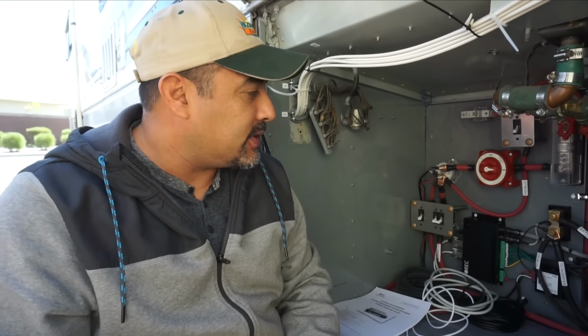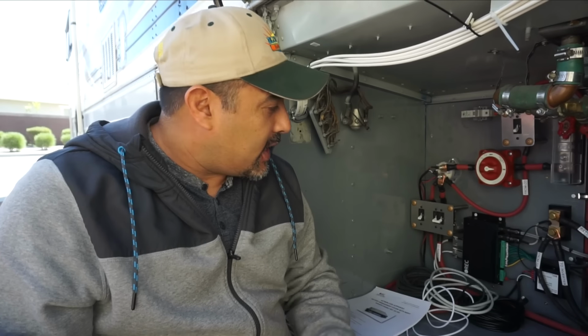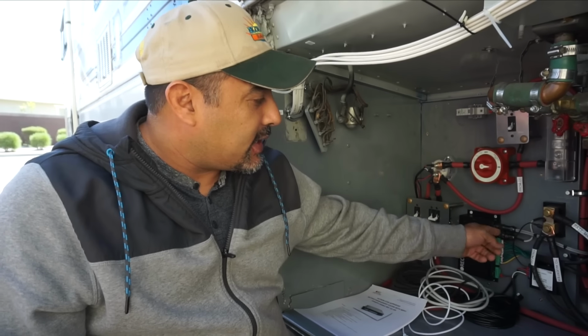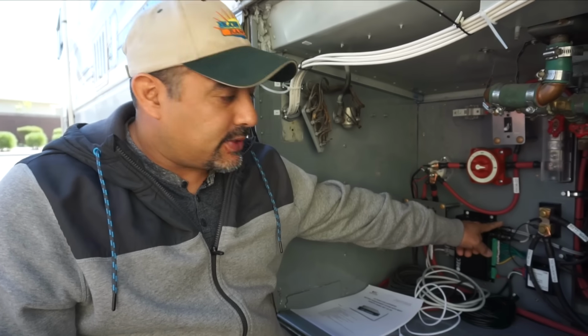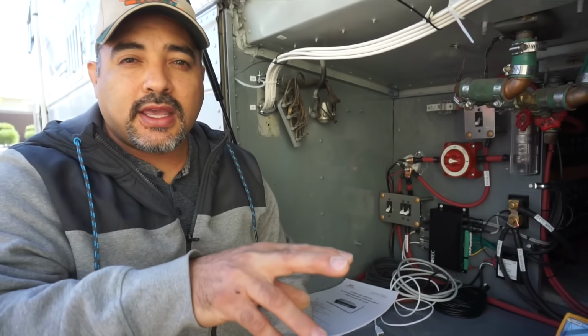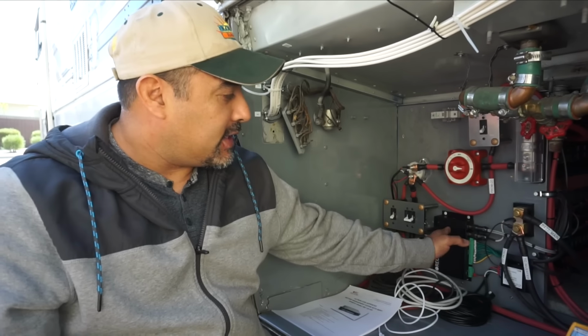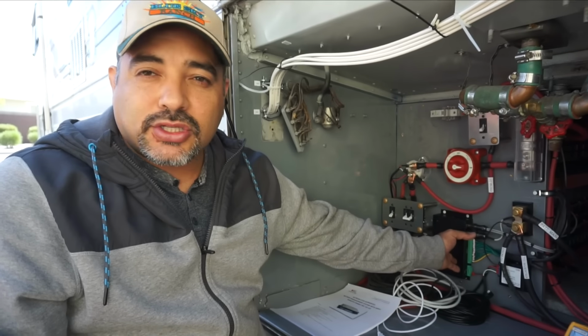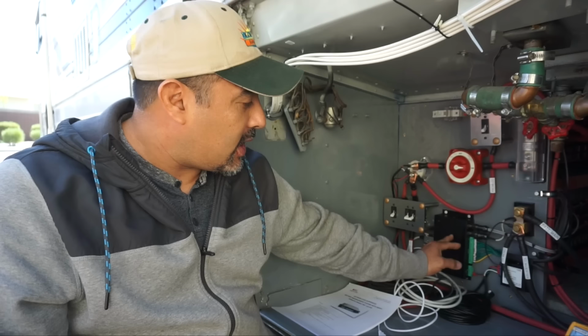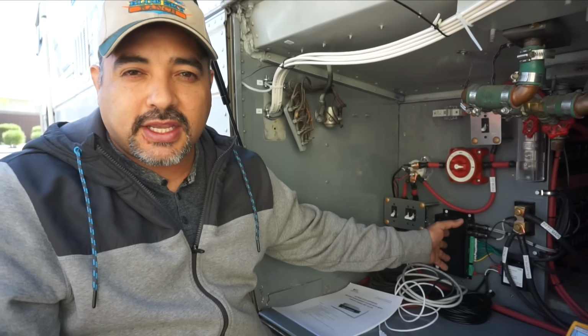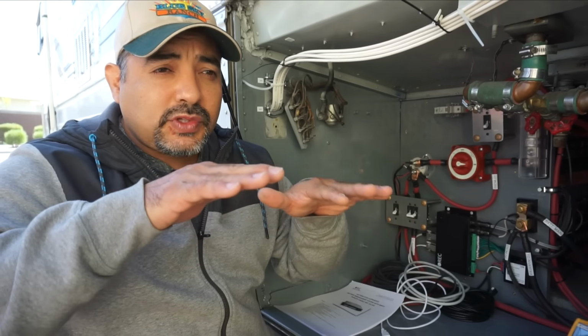Everything runs through the contactor. The other thing it does is monitor cell temperatures. There are 3 temperature probes in those batteries telling this BMS what the temperature is. It also has an internal temperature monitor, because this particular BMS also does cell balancing.